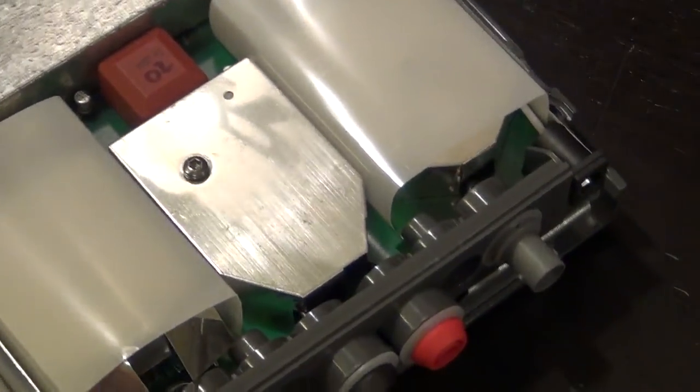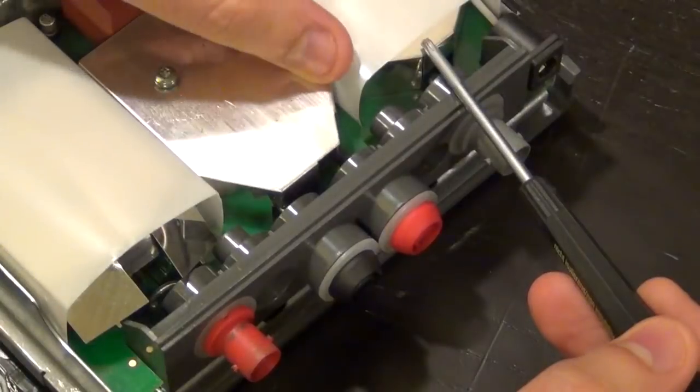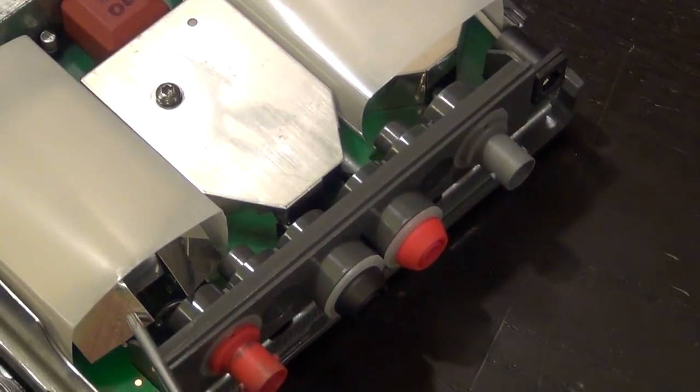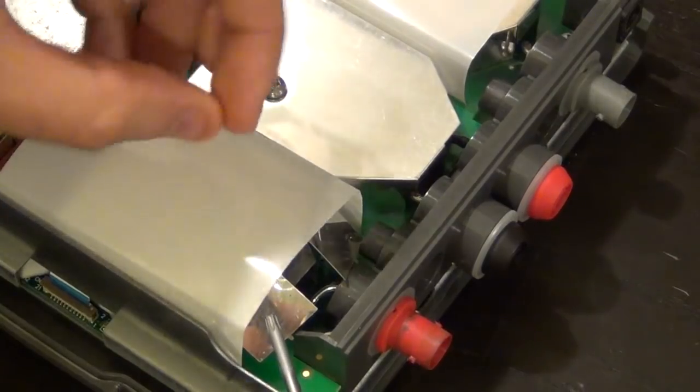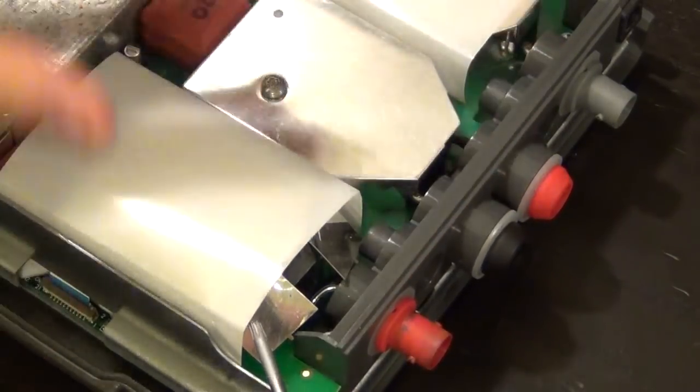And both the analog, or the RF channels rather, have a shield, an aluminum shield on top, which they should, of course. But this one, if you look, is not sitting in its correct place. It looks like something has crushed on top of this and has caused the aluminum cage to kind of flatten out.